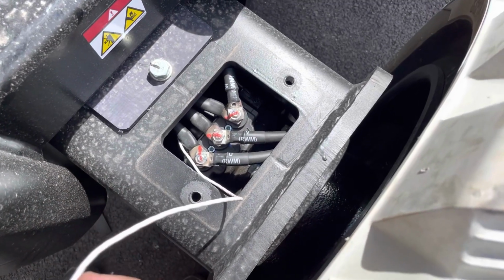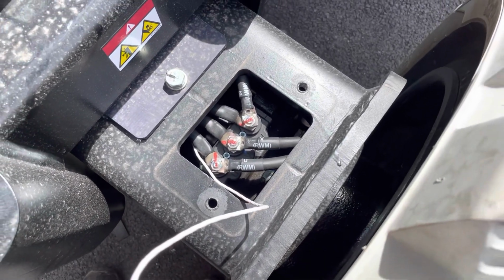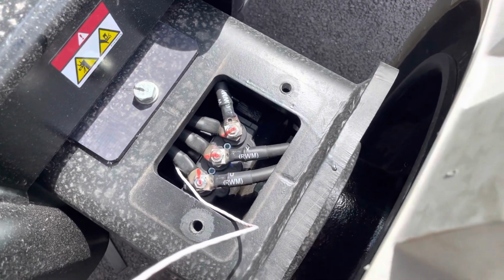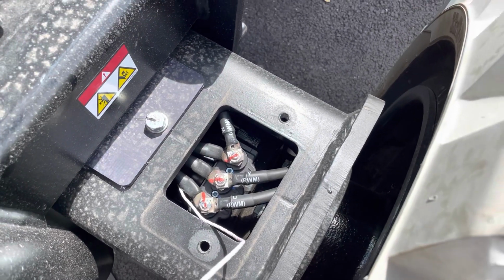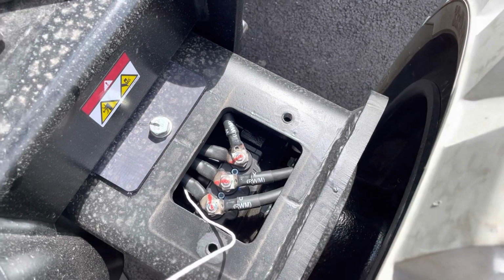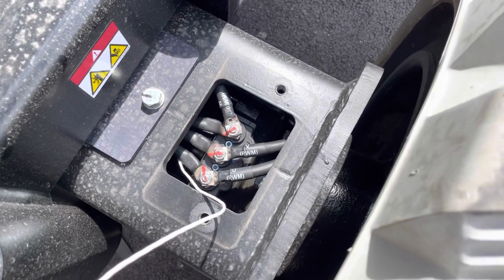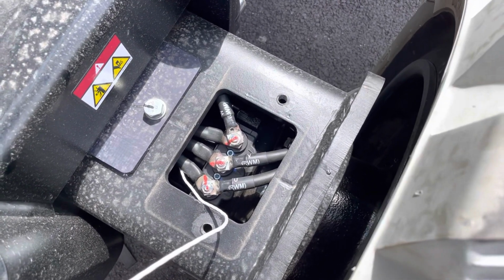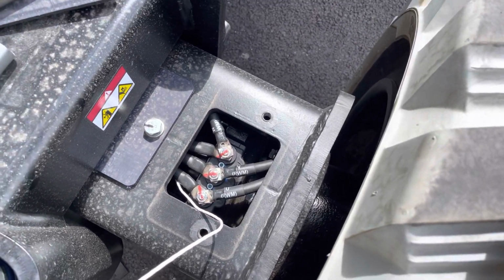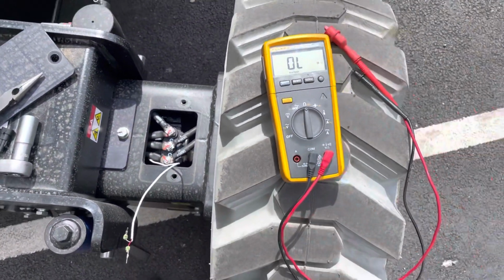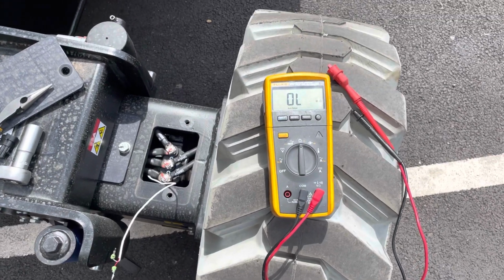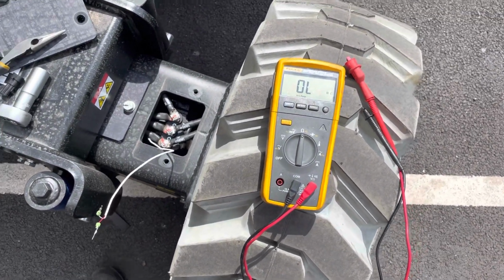And yeah, I think for now that is it. Needs the new motor. But if you would have the problem with the overheat fault, just check the resistance, and in a normal day, the ambient temperature of 20 degrees, you should have about 500 ohms, but this one is way too much.